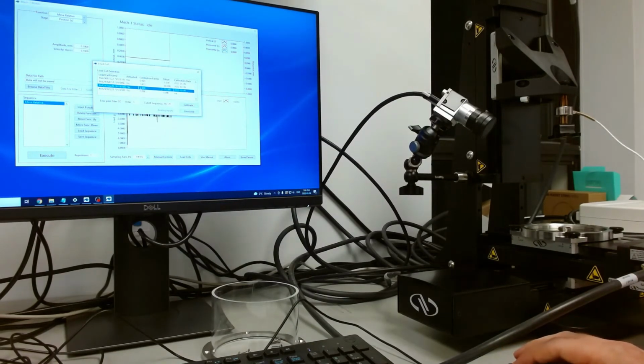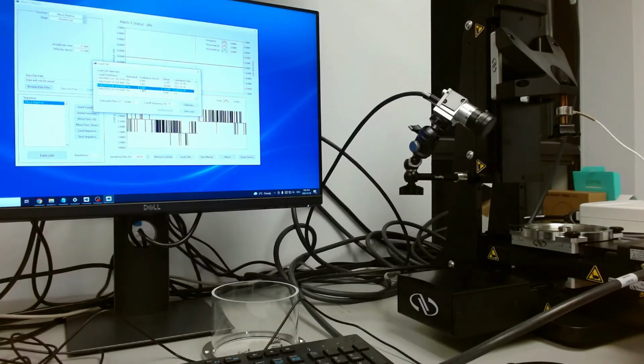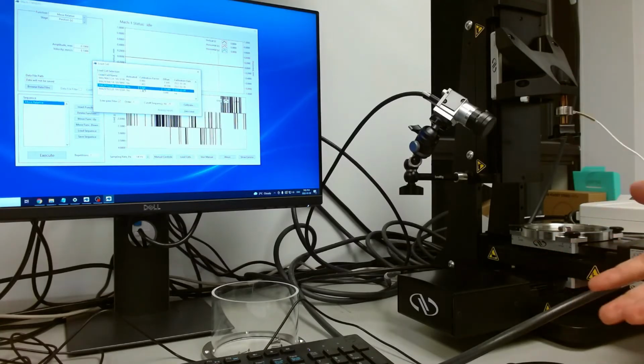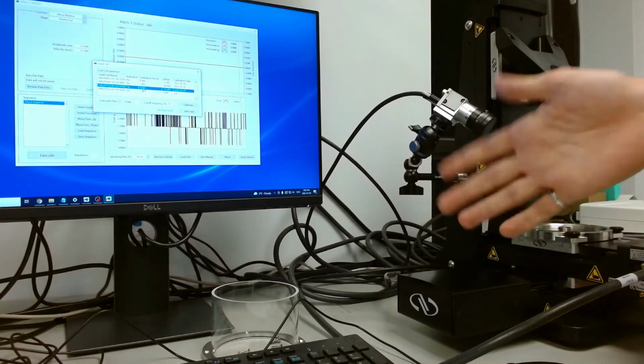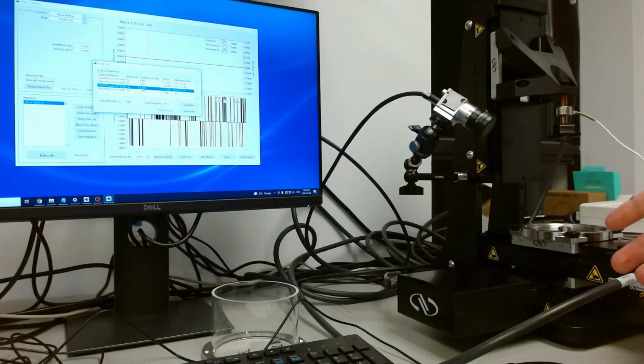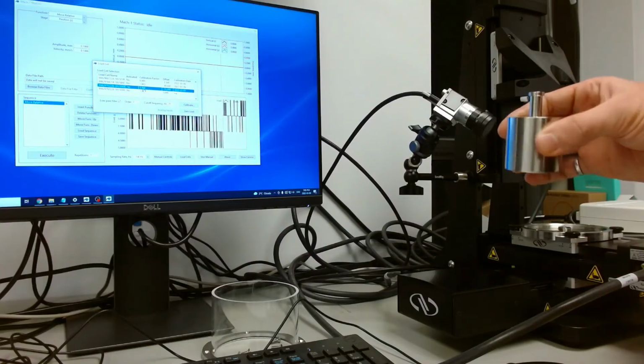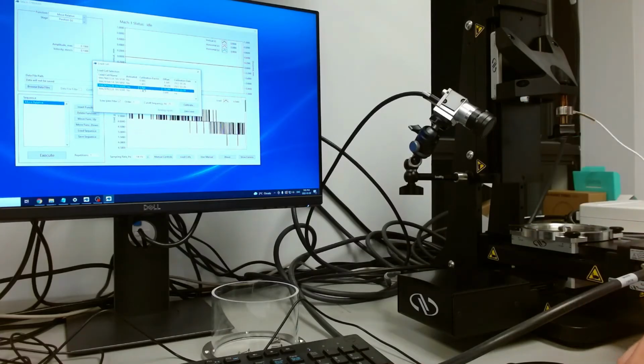The calibration factor we're looking for is around 1. If the number is much outside of 1, for example, over 5% over or under, 0.95 to 1.05, you can try the calibration again. It's possible that the weight was moving during the calibration, or if it's a consistent issue, you can contact.